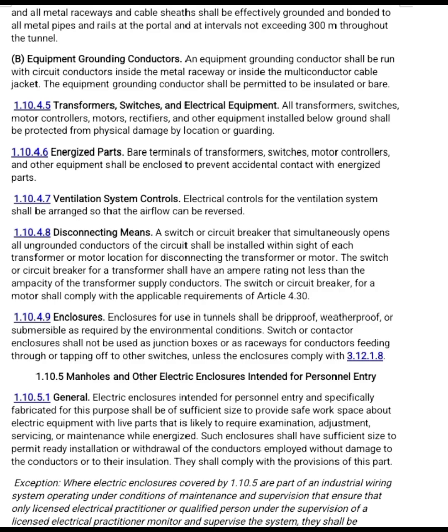B. Equipment grounding conductors. An equipment grounding conductor shall be run with circuit conductors inside the metal raceway or inside the multi-conductor cable jacket. The equipment grounding conductor shall be permitted to be insulated or bare. 1.10.4.5 Transformers, switches, and electrical equipment. All transformers, switches, motor controllers, motors, rectifiers, and other equipment installed below ground shall be protected from physical damage by location or guarding.